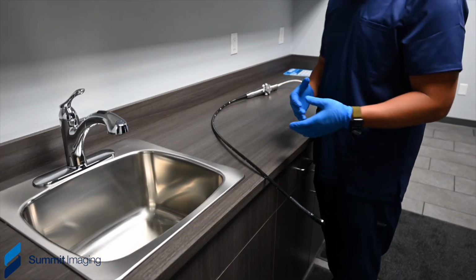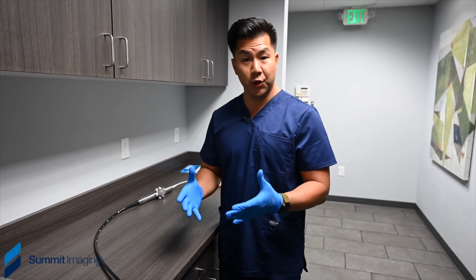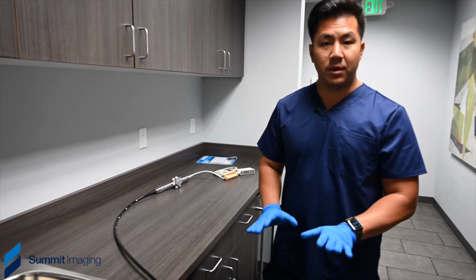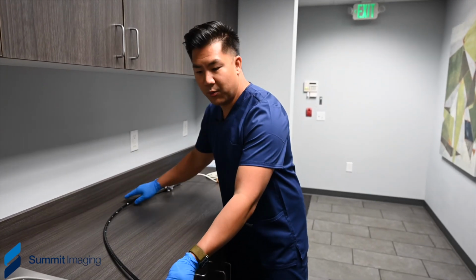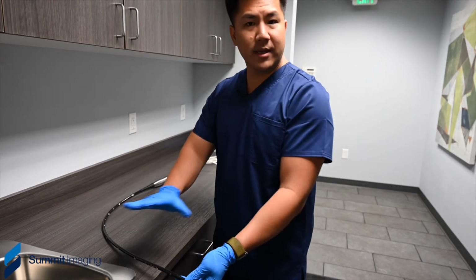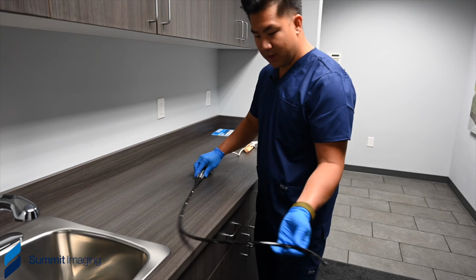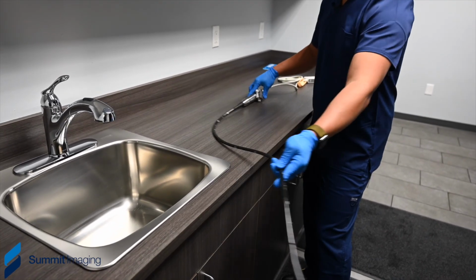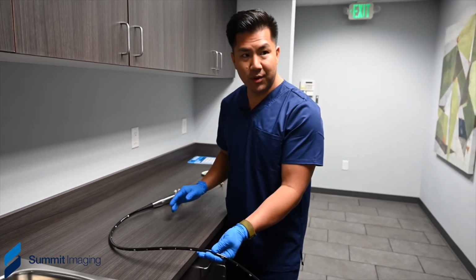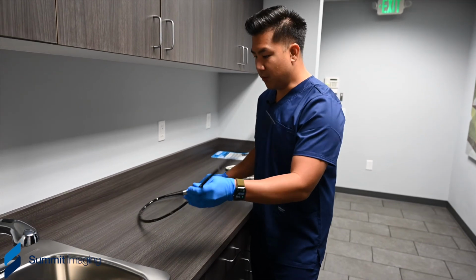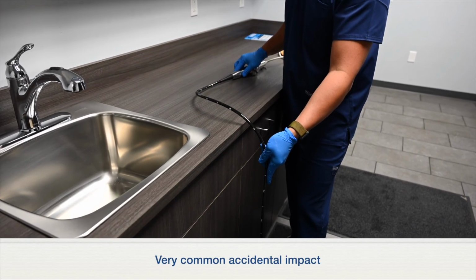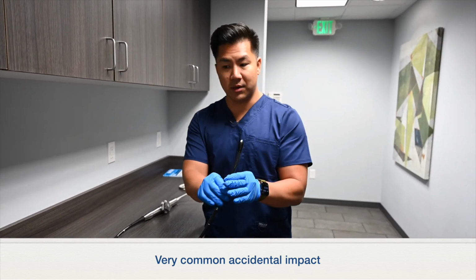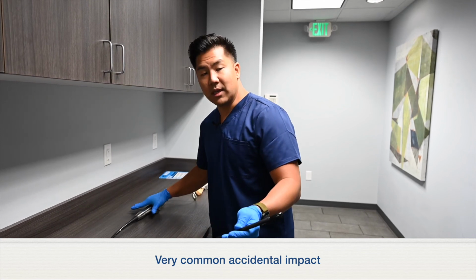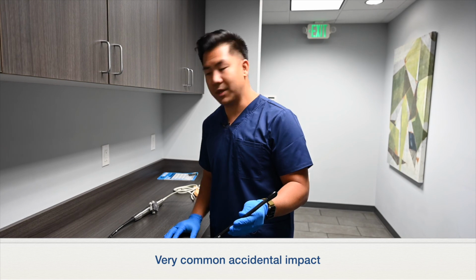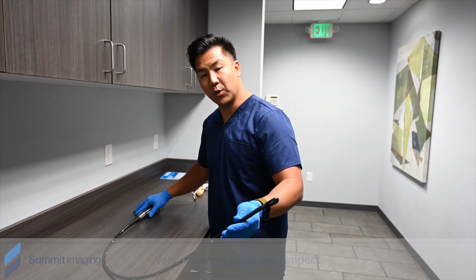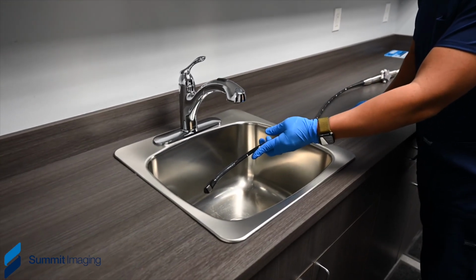So now we want to talk about decontamination as you're rinsing off this probe, getting all the debris and the fluids after a scan. And now it's here to be rinsed off essentially. And we have it on a table here, but here's one thing that we've seen a lot. Things are wet, things are slippery, and what happens is this will move around, and as you move the handle around, you can see how much it moves the rest of the insertion tube around. Well, because things are slippery, wearing gloves, the probe will slip and bang the side of the cabinet. That's enough to obviously disrupt the electronics on the tip. So we highly recommend this is stable. We've seen contraptions at healthcare facilities instituted after we've been there to hold this handle here and then controlling where the tip's going to eventually be.